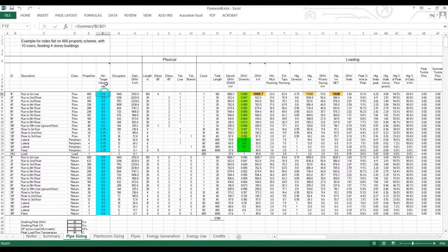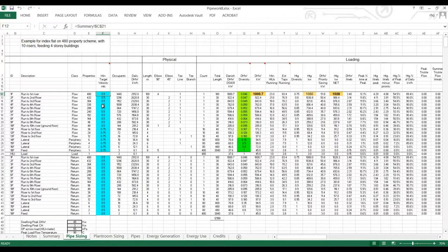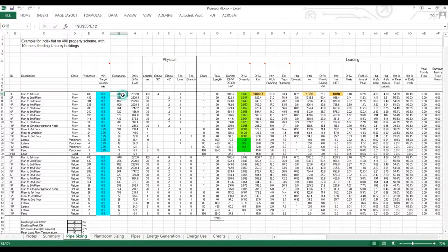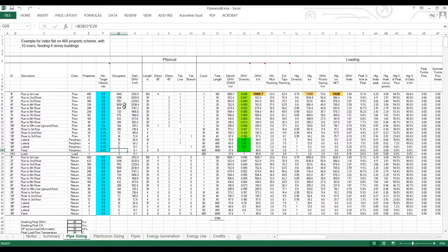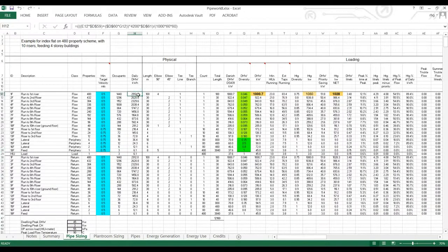We have the minimum target velocity. So this is used to select pipes. It will pick the pipe size that matches this minimum velocity or the pipe size smaller. We have the number of occupants downstream. That's three occupants per property, multiplied up. We have the daily hot water use. This comes from the number of occupants.